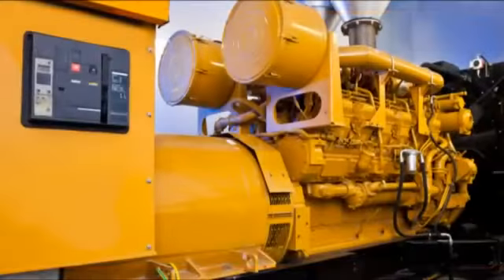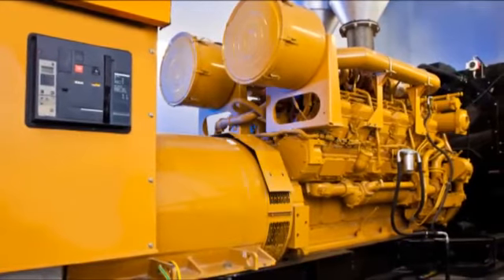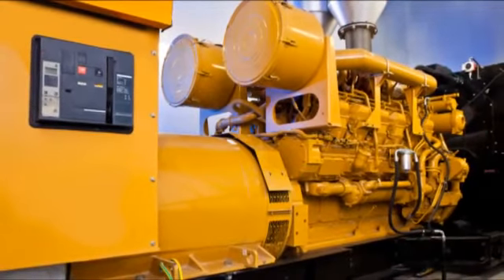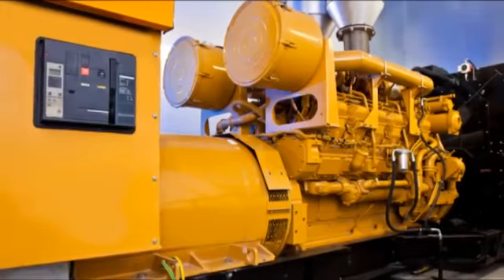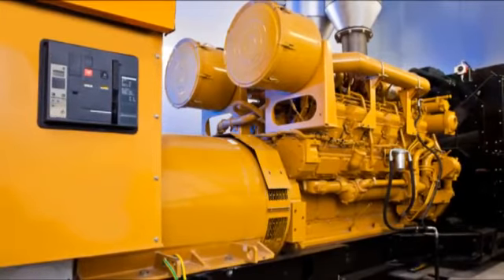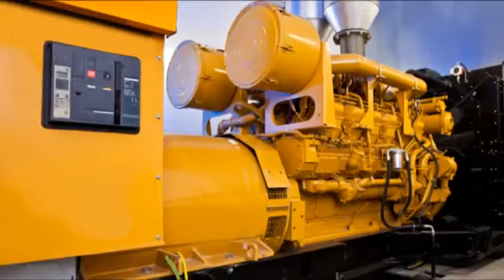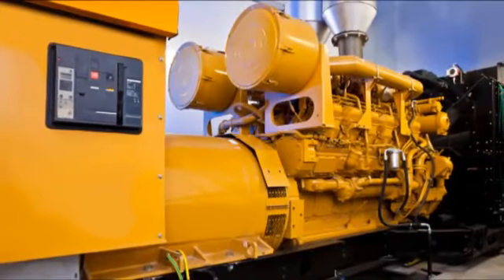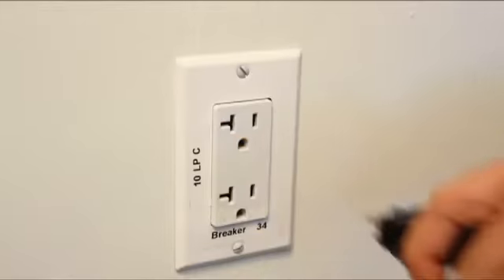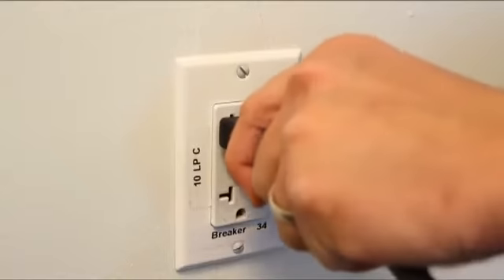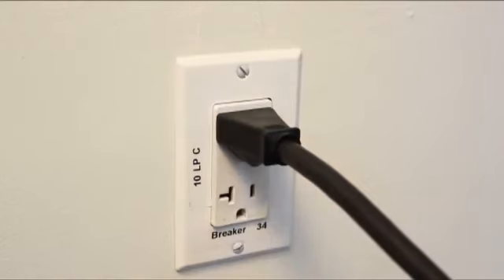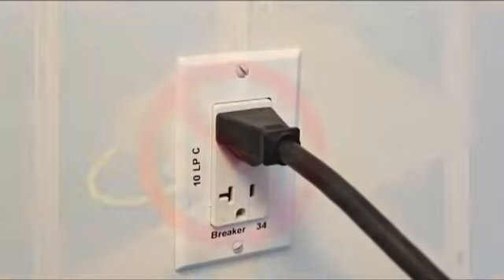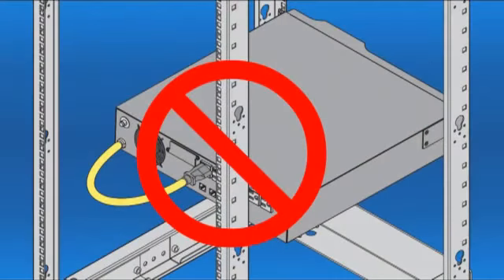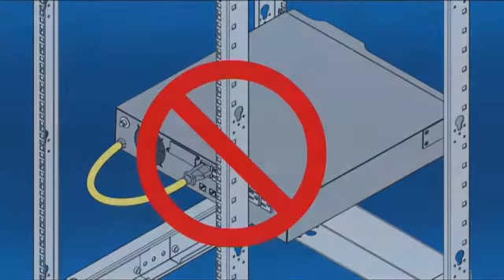If you connect your UPS directly to a motor-powered AC generator or to a wall outlet that is supplied by a generator, the generator must provide filtered, frequency-regulated, computer-grade output. Connecting your UPS to a generator may affect its ultimate lifetime warranty. Connect your UPS to a properly grounded AC power outlet. The outlet that supplies the UPS should be near the UPS and be easily accessible. Do not connect your UPS's input to its output. This will damage the UPS and may affect your warranty.